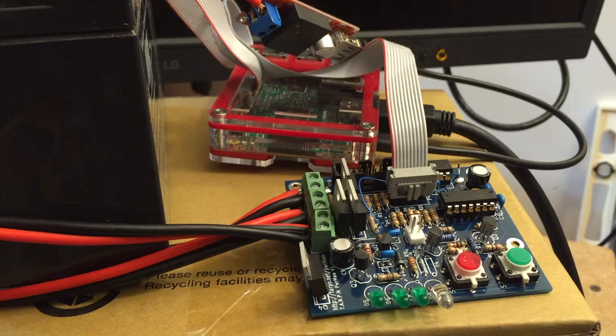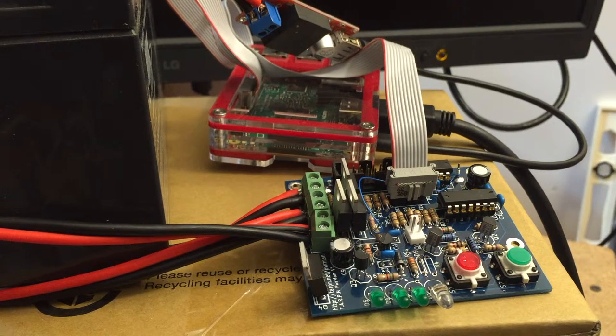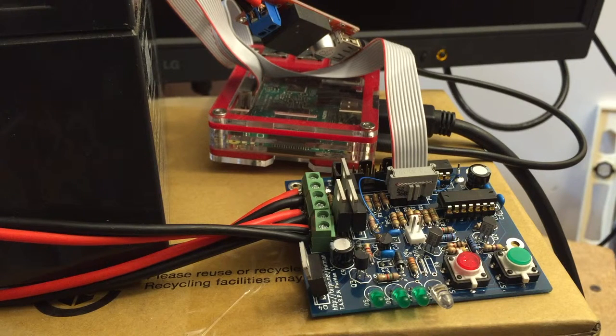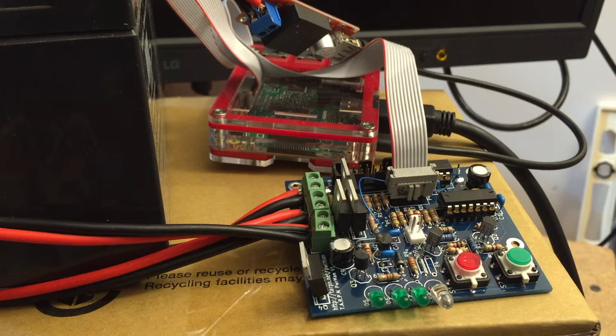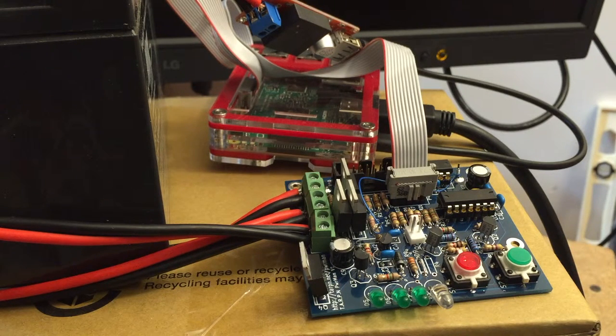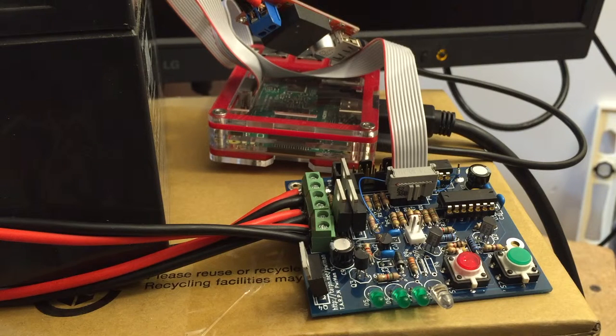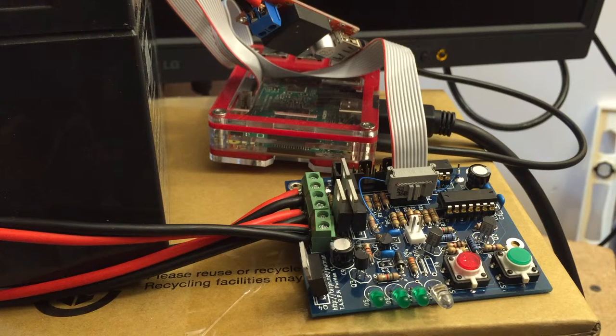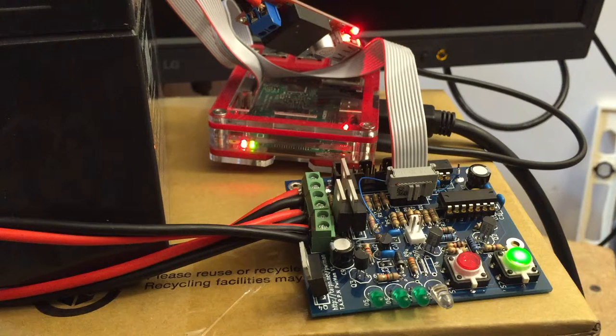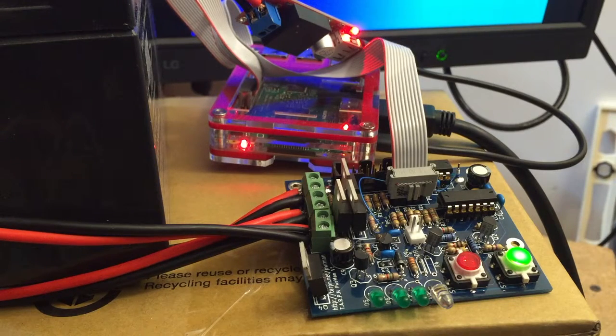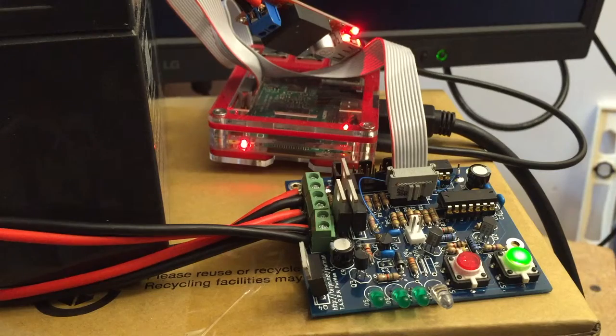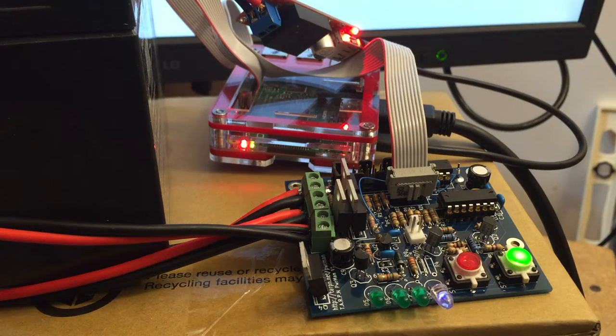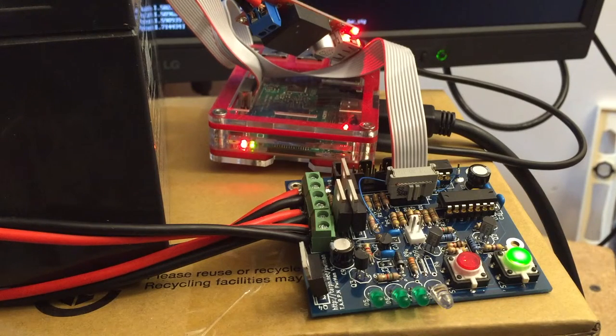The PowerMan is in battery mode, so it's blinking very slowly. Interestingly, because we yanked power and the unit shut down automatically, it will remember that it was supposed to be powered up. If I reapply power now, it will come back up automatically to restore the node operation. If, on the other hand, I had shut it down by hitting the red button, it would not have come back up automatically when power was removed and reapplied.